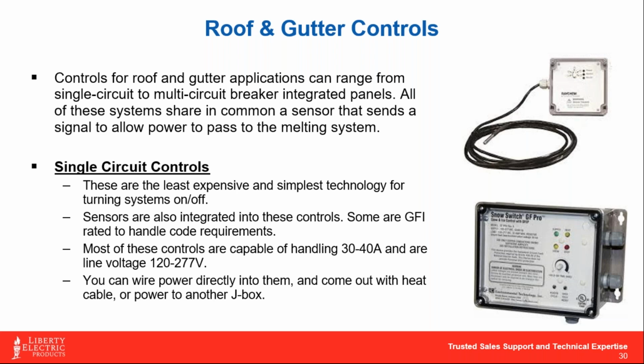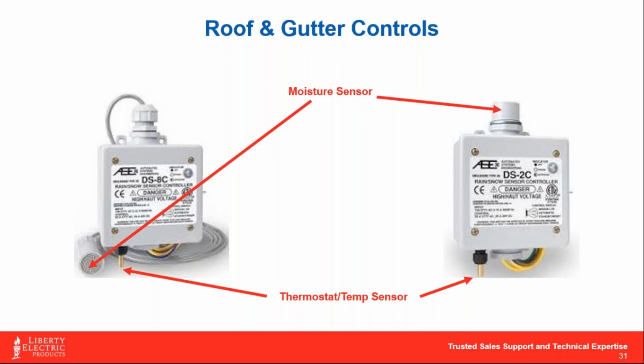Most of these manufacturers, their controls are going to be very similar in terms of default settings and what they're really looking for between moisture and temp. You can get these things also in a GFI rated version or a non-GFI rating. Again, it's price pointing. What is nice about these is that they act as J boxes. You can literally bring power into one side of this box. You can come right out of it with your heat cable run. And as you can see from the graphics here, those are the sensors that you would just place accordingly in the best location for them to get hit with snow.